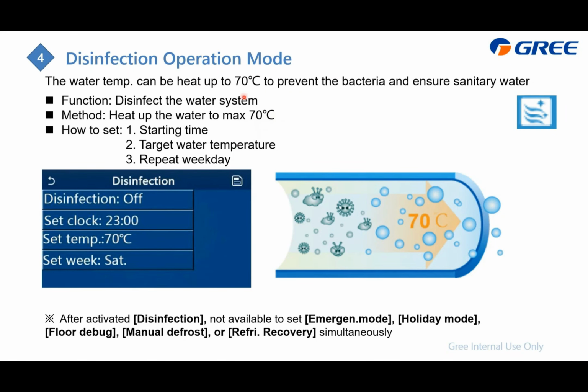And here is a heads up: the heat pump only goes up to 55, and anything higher than this temperature relies only on the water tank heater, which means if you don't have this water tank heater, the system cannot heat up the DHW higher than 55 degrees.